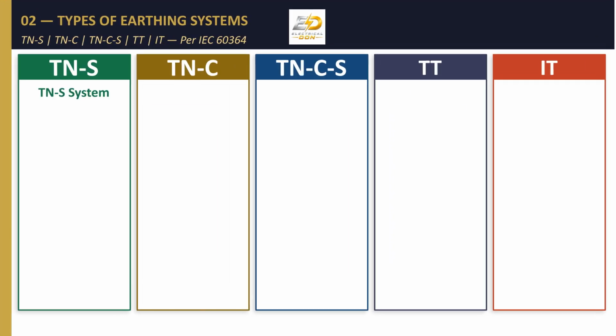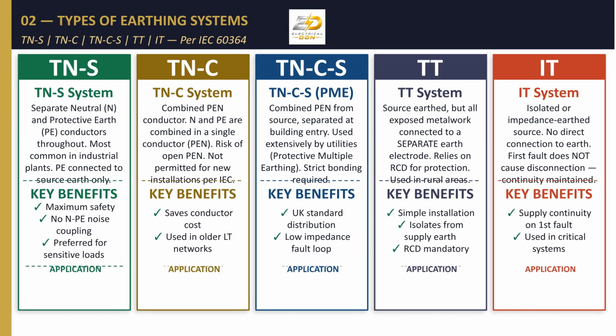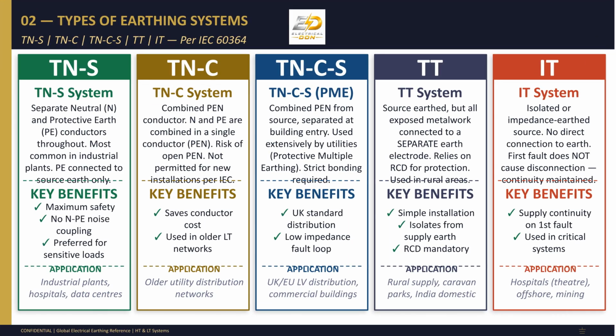We review 4 main earthing systems per IEC 60364. TNS offers maximum safety with separate neutral and earth conductors. TNC combines them, but new installations are restricted. TNCS is common in the UK and Europe. TT uses separate earth electrodes, requiring residual current devices for protection. IT systems are isolated for continuity in critical operations.